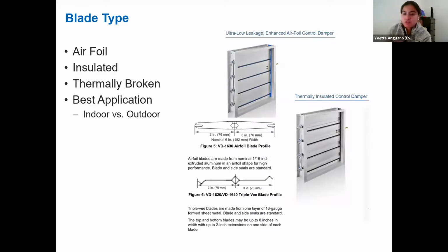And then in terms of actual blade types for the dampers, you've got low leakage, insulated, thermally broken. So for that low leakage airfoil damper, typically you just have your aluminum and cap blades. And then if you go to the next step up, which would be the insulated blades, those blades are constructed with that same aluminum shell, but they're injected with a polyurethane foam, which would help in terms of isolation and just that insulation.